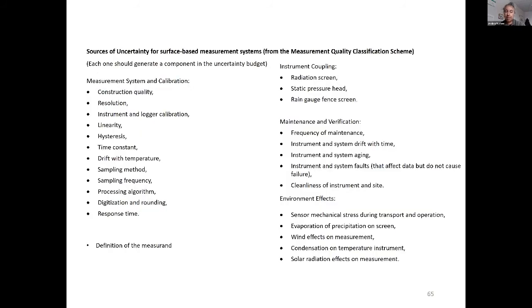It talks clearly about sources of uncertainty for surface-based measurement systems, which are grouped again into the calibration, the definition, the coupling, the maintenance, and the environmental effects. I won't go into all of them, but please give a look at this, including, for example, the frequency of maintenance is part of your uncertainty. The drift with time, the aging, it's becoming old. The paint is no longer very reflective, the salts, and so on.